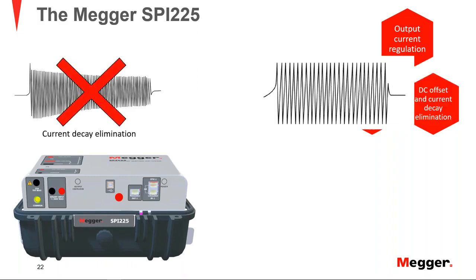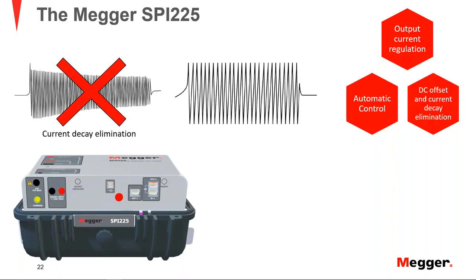So the SPI will constantly check or measure the impedance in the measuring circuit while it is testing. It will guarantee a constant current for the test, and thus give me more accurate results for those injections that take several seconds.